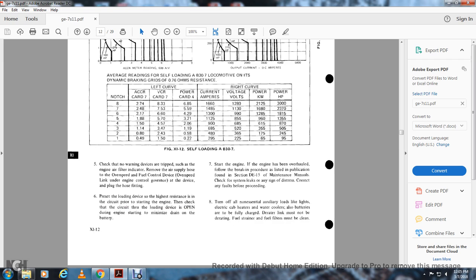Check that no warning devices trip, such as the engine air filter indicator. Remove the air supply hose, the overspeed fuel control device, and the overspeed linkage under the engine control governor at the device, and plug the hose fitting. Preset the loading device for the high resistance of the current circuit prior to starting the engine. Check that the circuit through the loading device is open during engine starting to minimize the drain on the battery.